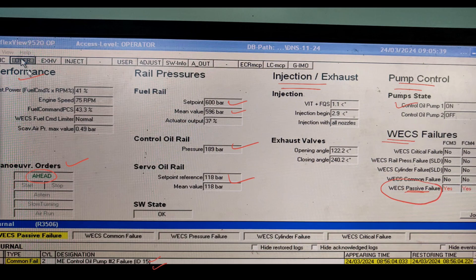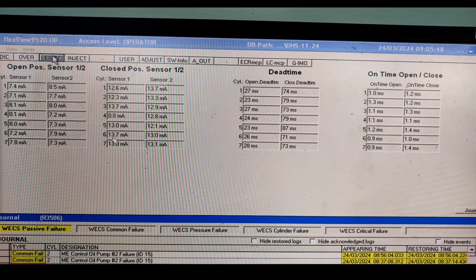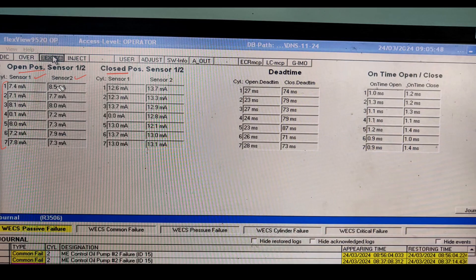In the Exhaust option you can see both sensor open and closed positions - these are stroke sensors fitted on each unit. There are seven cylinders, so seven sensors are installed with two sets each for opening and closing. You can see the open and close timing here. More detail about these parameters will be covered in the next video.